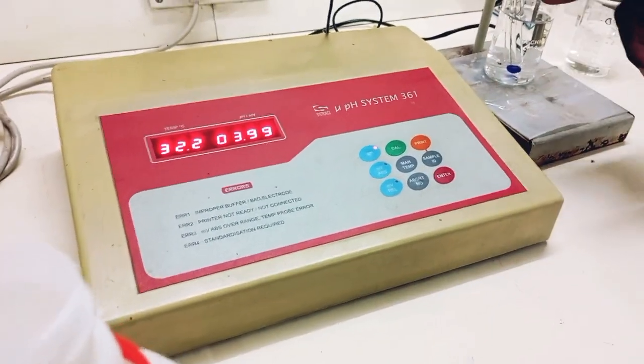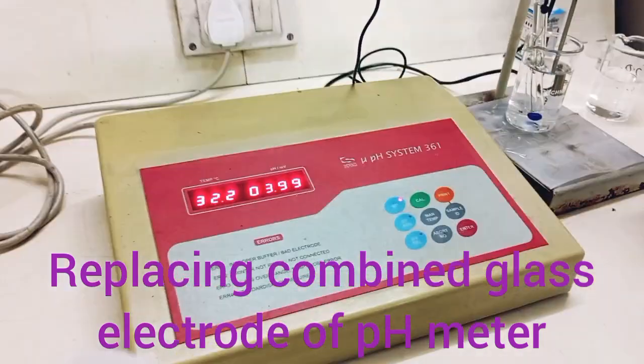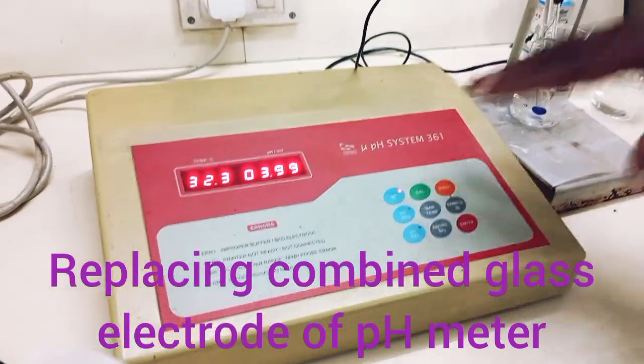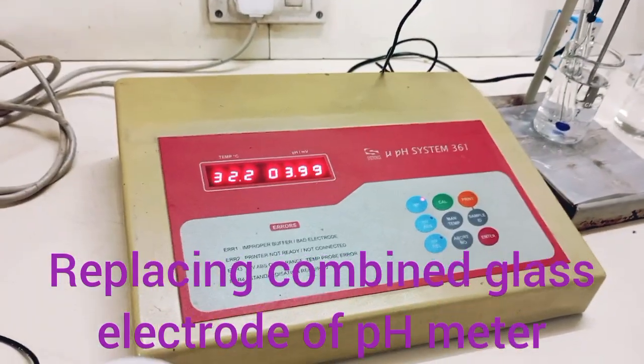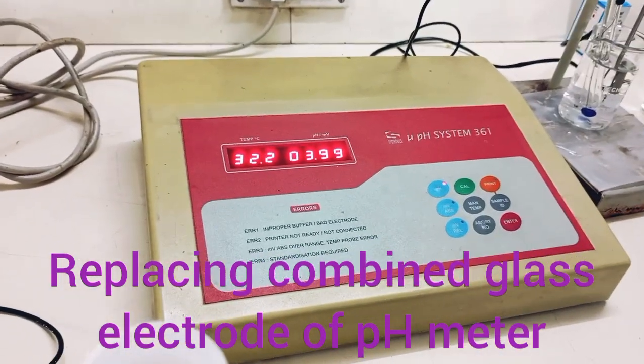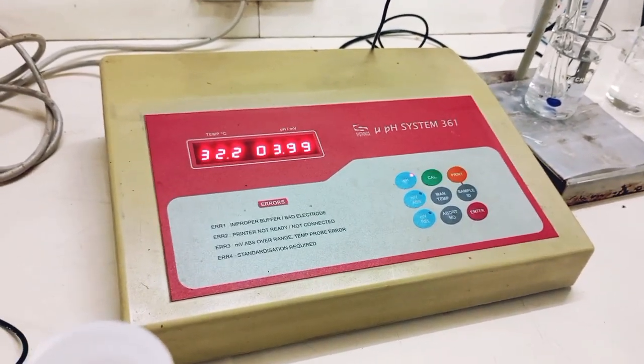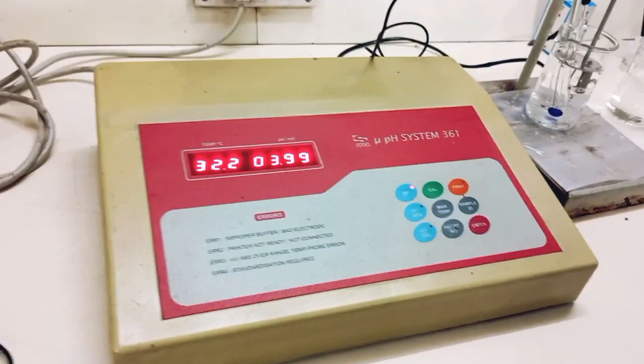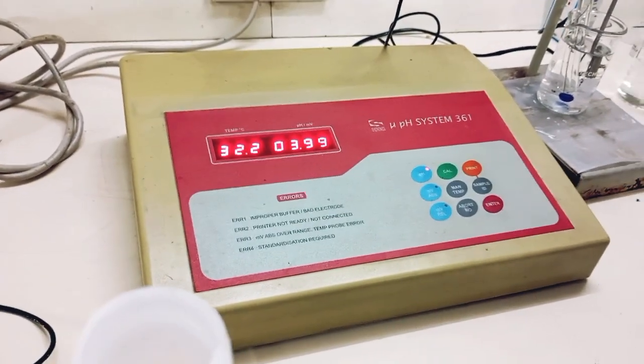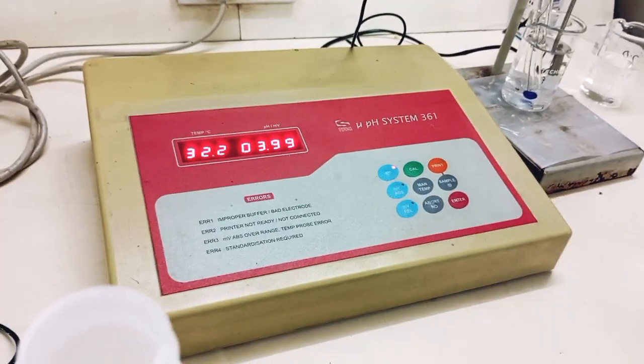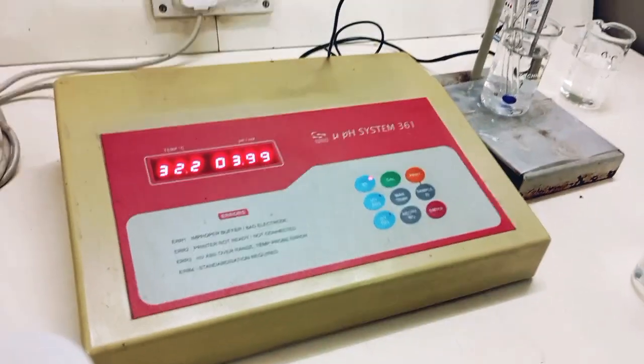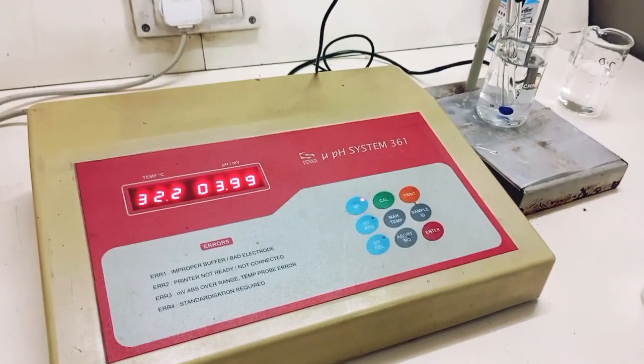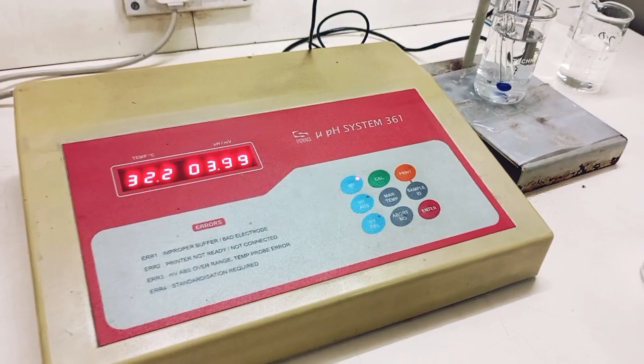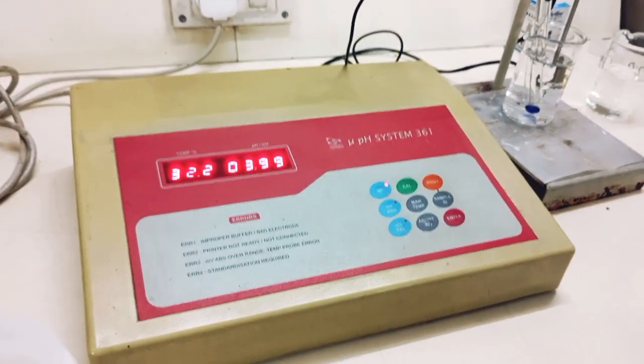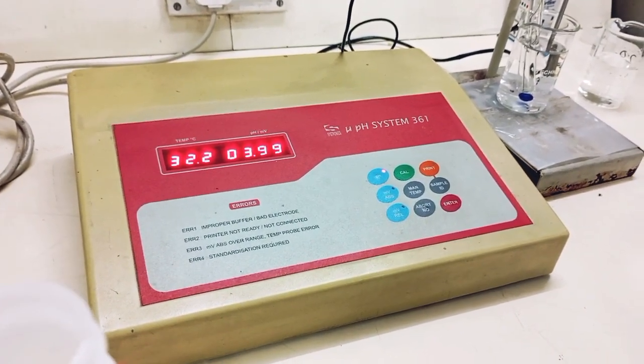For that purpose, it is very important to stick to the technician who supplied the machine or who manufactured it. The branded electrode will give you beautiful results. Otherwise, the machine will not get calibrated well, and there is a question mark over the accuracy of the reading you will see. So better, guys, this machine, pH Systronic 361, I am keeping for more than 18 years and it is working well. Take care.